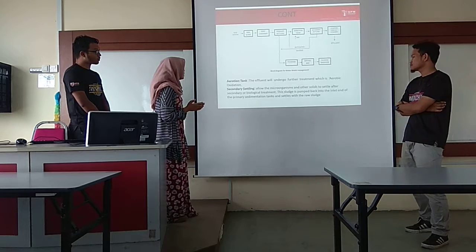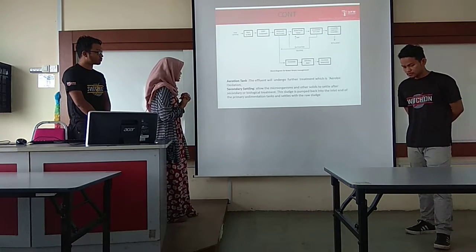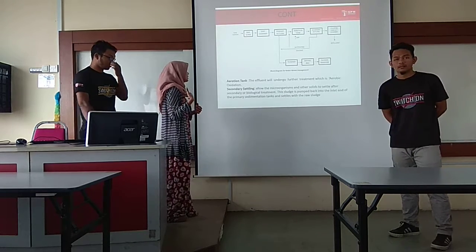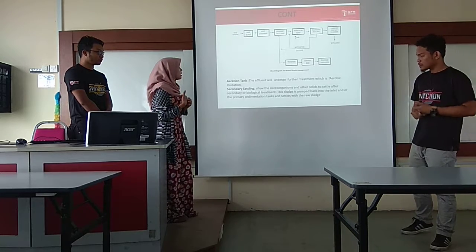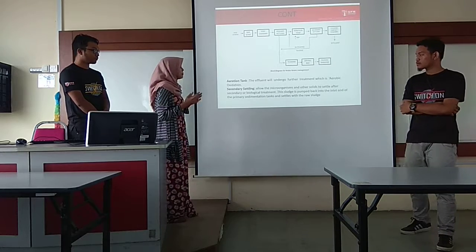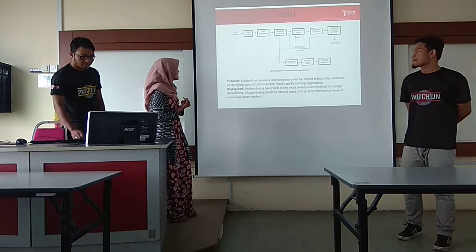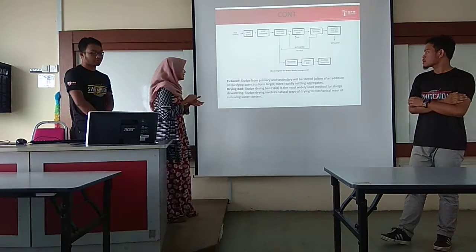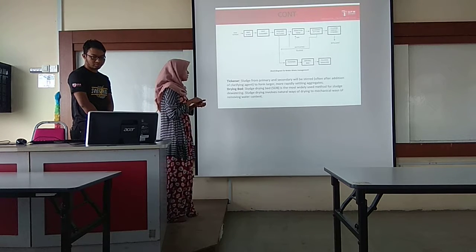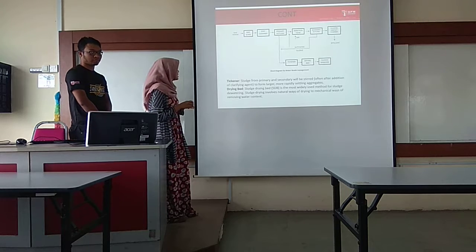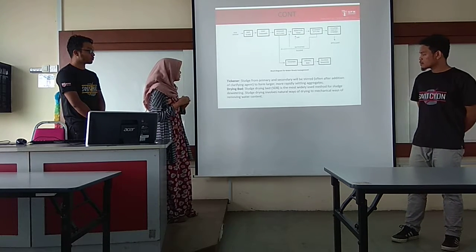For secondary treatment, the sludge will undergo an aeration tank where the influent will undergo aerobic oxidation. After that, it will be transferred to secondary settling, which allows the microorganisms and other solids to settle. After secondary or biological treatment, this sludge is pumped back into the inlet end of the primary sedimentation tank. Sludge from primary and secondary will enter the thickener, where it will be combined with clarifying agents to form larger, more settling aggregates. Lastly, the sludge drying bed is the most widely used method for sludge dewatering.